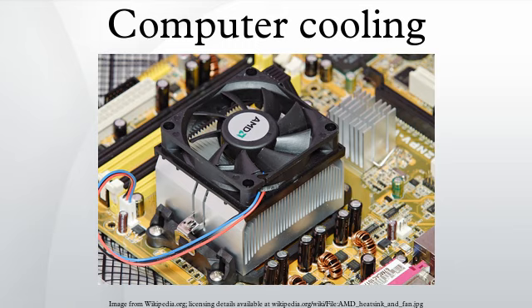A heat exchanger might still be needed though, and the piping also needs to be placed correctly. Extreme component density supercomputers such as the Cray-2 and Cray-T90 used additional large liquid-to-chilled liquid heat exchangers for heat removal. The liquid used must have sufficiently low electrical conductivity not to interfere with the normal operation of the computer. If the liquid is somewhat electrically conductive, it may be necessary to insulate certain parts of components susceptible to electromagnetic interference, such as the CPU. For these reasons, it is preferred that the liquid be dielectric.